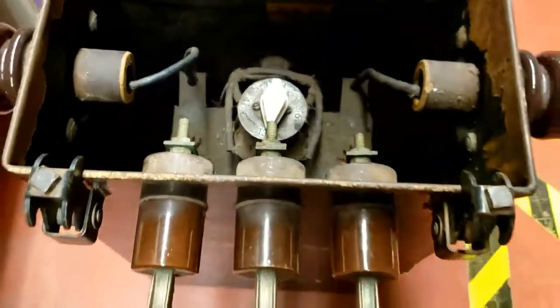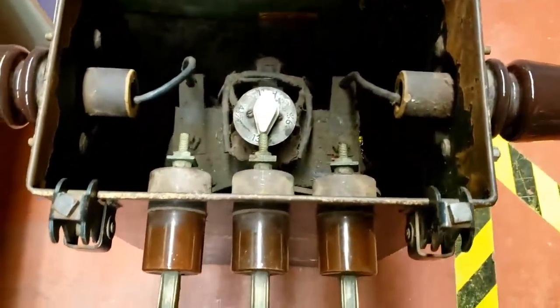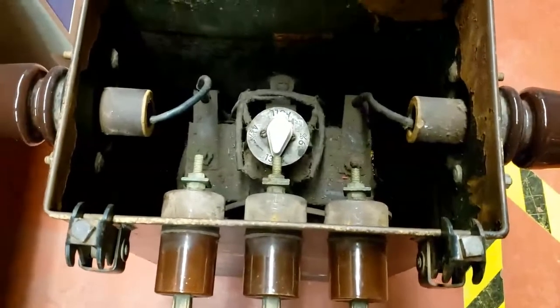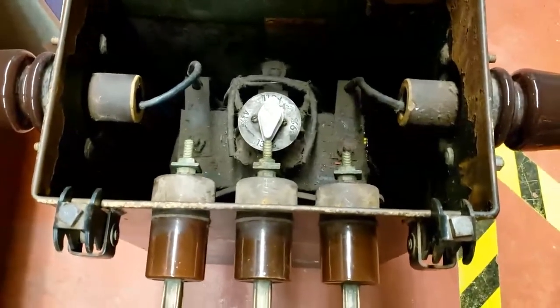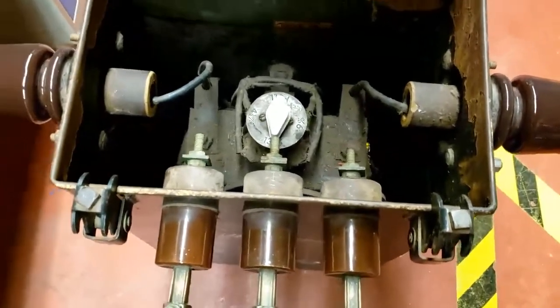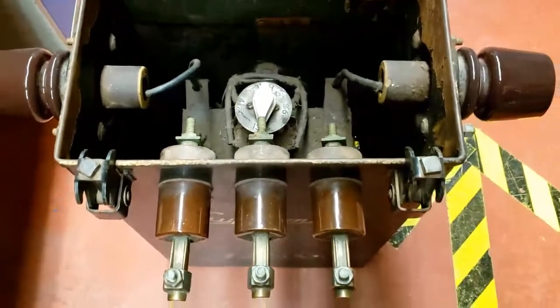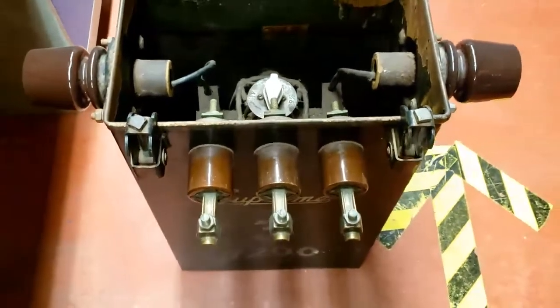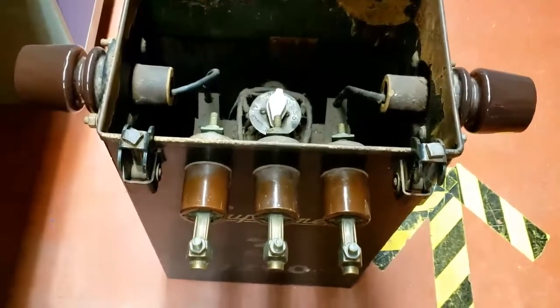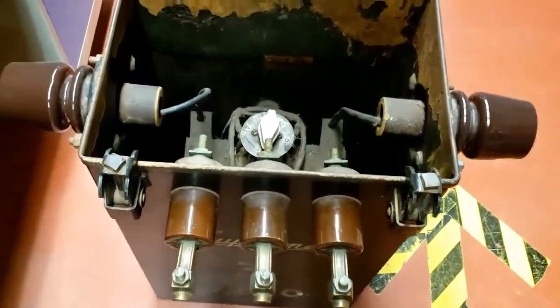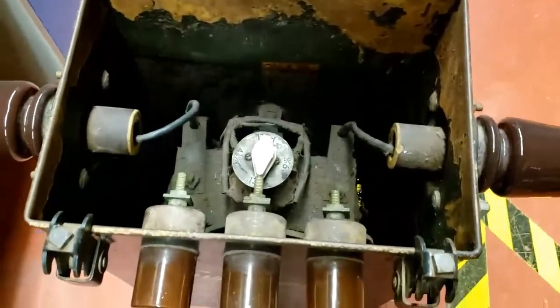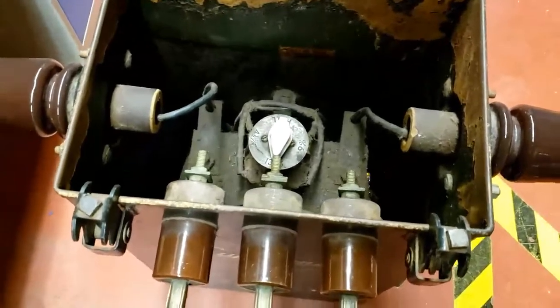4.5% actually. So what that does on a long road, these lines are running down the highway for kilometers. At the far end, the line loss is going to drop the voltage to the customer. Customer might not get 240 volts, so they might get 220 or 210. So you can use this tap changer just to boost the output up a little higher.